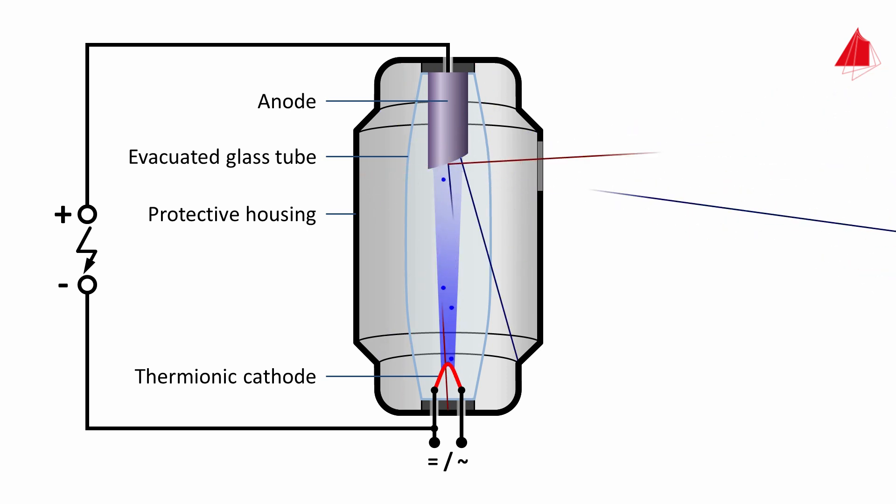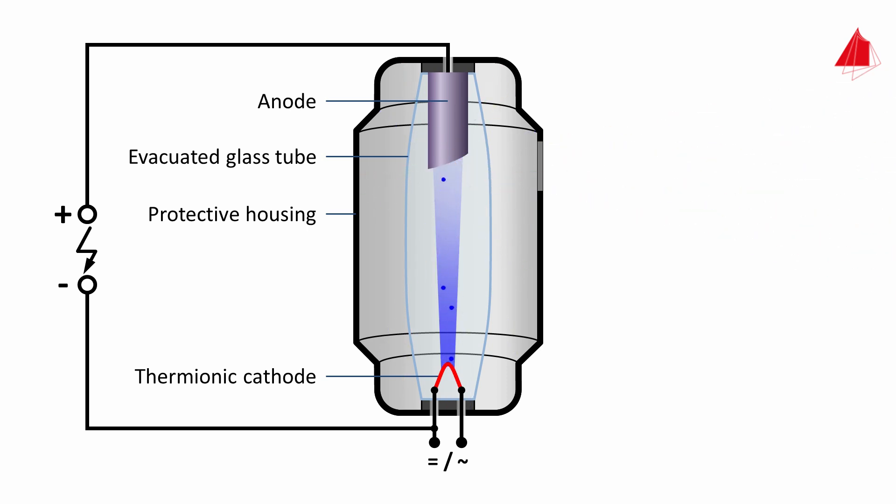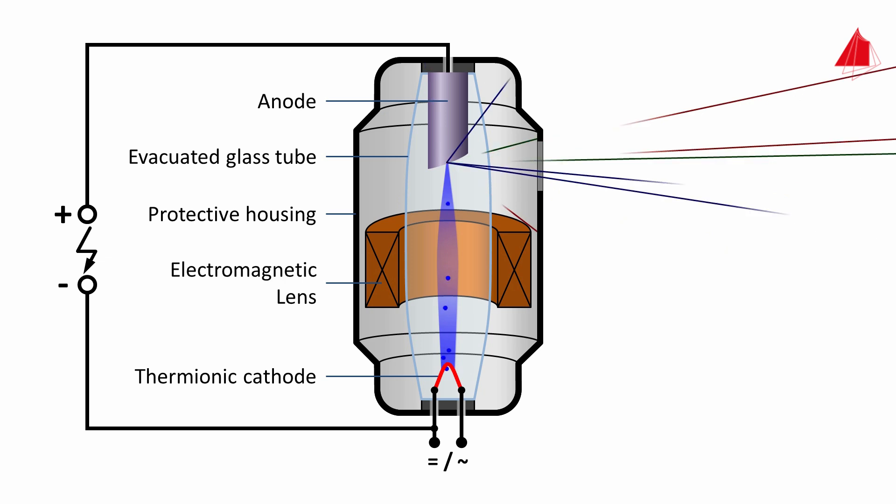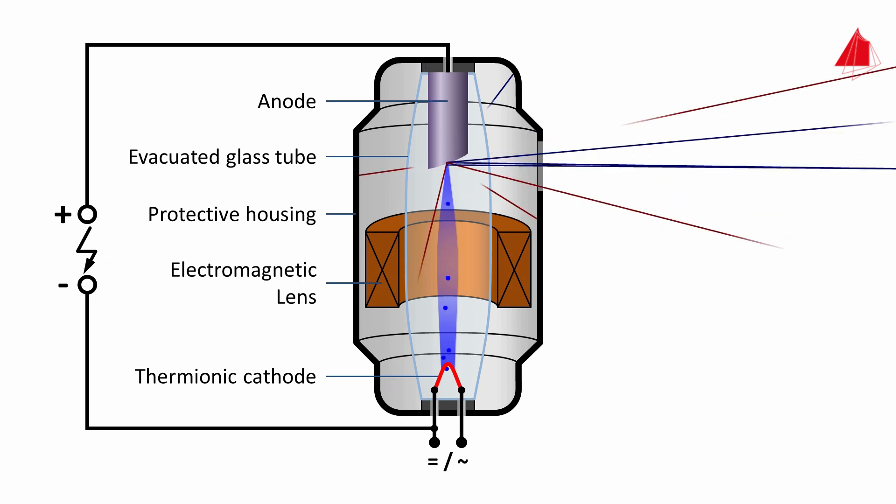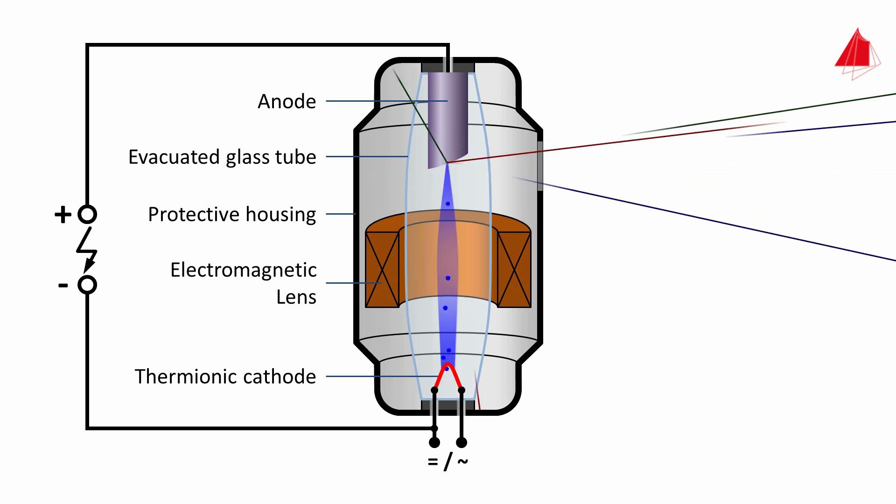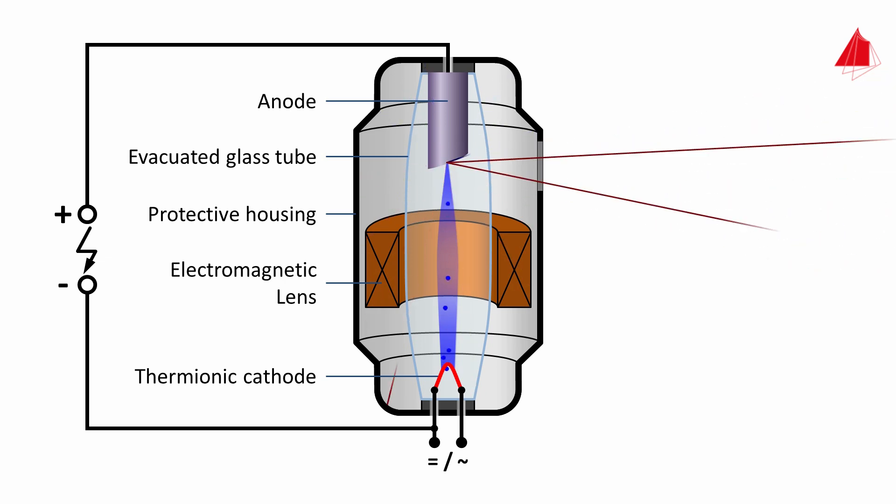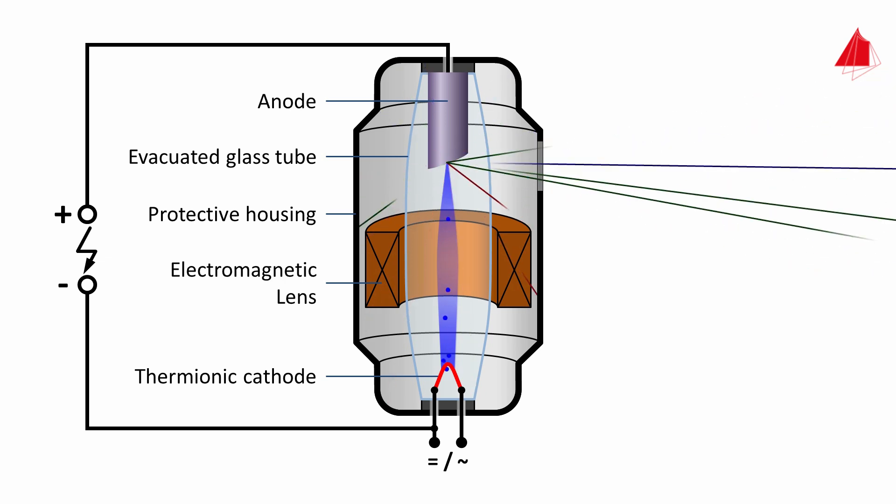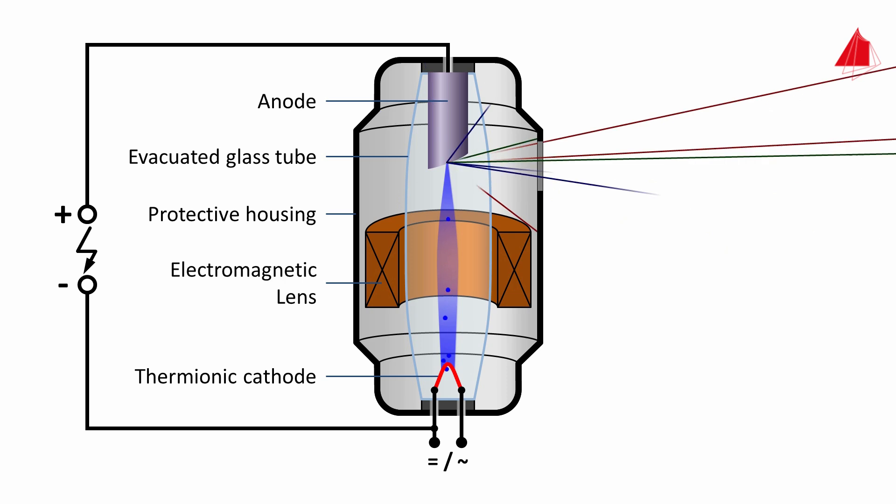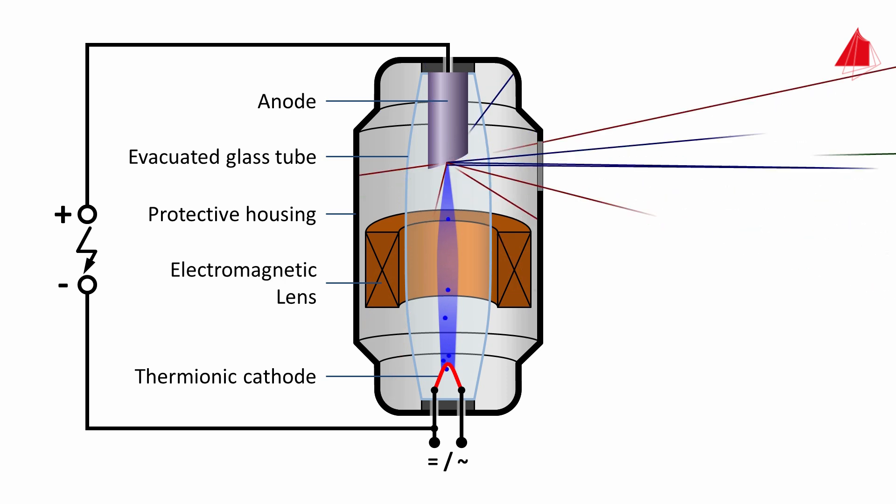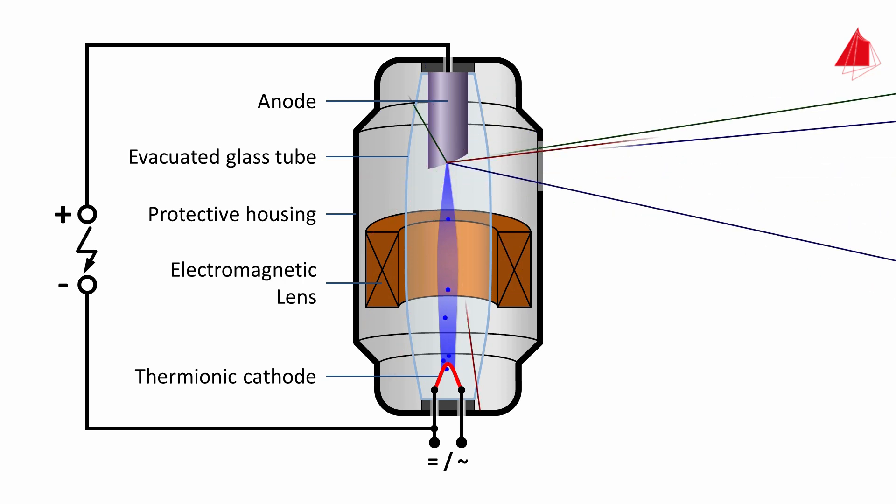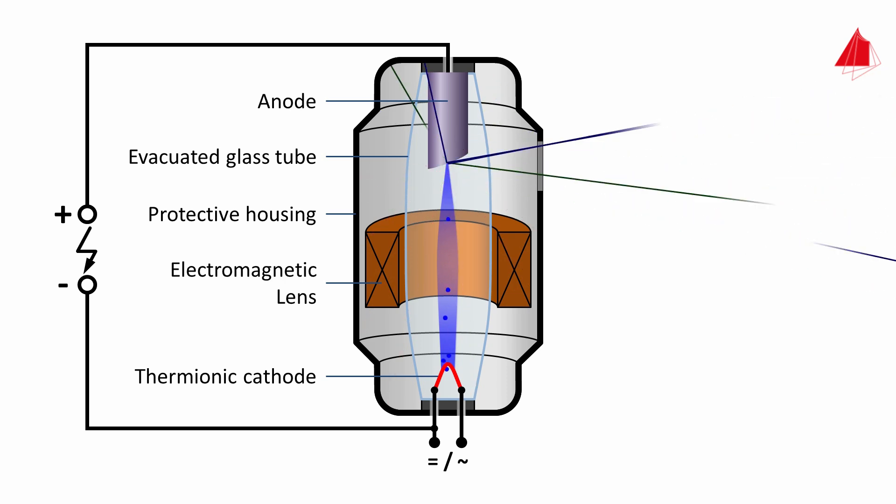To solve the problem, an electromagnetic lens is used to focus the electron beam at a small spot on the anode surface. The smaller the focal spot, the sharper and higher in contrast the x-ray image will be.